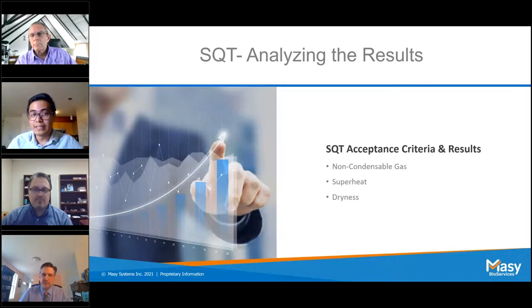Next is dryness testing. The logic behind dryness testing is to test how wet the steam is. If the steam is too wet, the sterilization assurance level will most likely not be met, and you may get false sterility. In order to meet EN285's criteria, you need a dryness level of 95% or more by weight. And then lastly, we'll dive deep into superheat, which is the temperature of steam above the temperature of saturated steam for the moisture content. Basically, if the temperature is too high above the moisture content, then you may experience melting or damage to the equipment you desire to sterilize, which is meant for dry heat sterilization. The acceptance criteria for superheat per EN285 is less than or equal to 25 degrees Celsius. These tests, again, require passing results in triplicate to support sterility in regards to proving consistency and reproducibility. I'm now going to pass it back to Rob to discuss recommendations for steam quality testing.